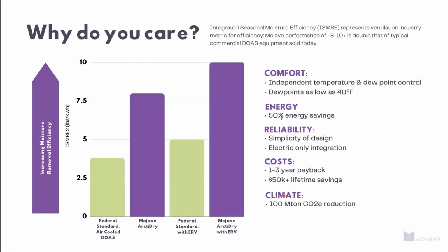So switching gears a little bit, why do you care about all of this? Those federal minimums I showed you a couple slides ago are these green bars on the graph. So 3.8 pounds per kilowatt hour of moisture removal efficiency without an ERV, 5 pounds with. Mojave ArctiDry is pushing 8 pounds per kilowatt hour of moisture removal efficiency without an ERV, and 10 pounds plus with. Now, additionally, because we've paired together DX technology with liquid desiccant technology, we've effectively decoupled our dry bulb and dew point control. So Mojave ArctiDry can take a dry bulb set point and a dew point set point and control each with our system.